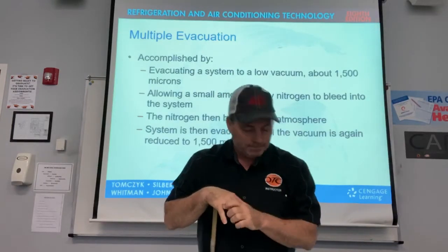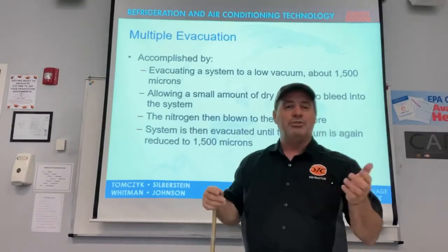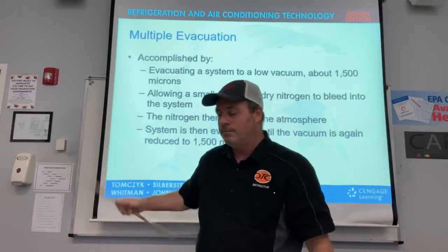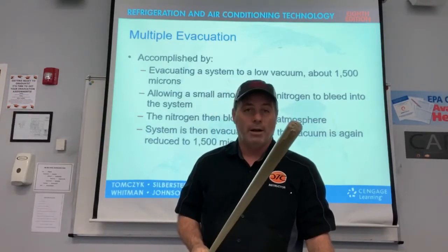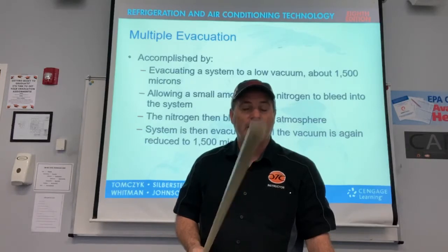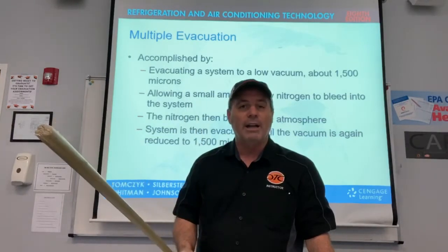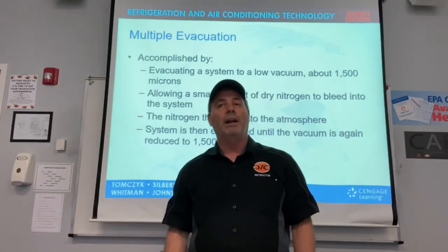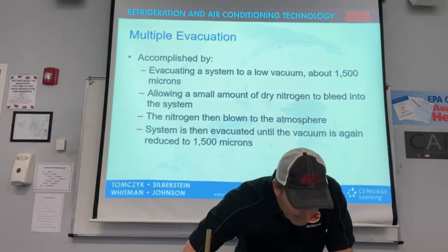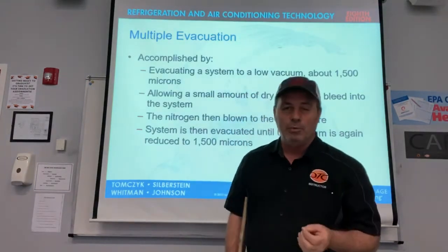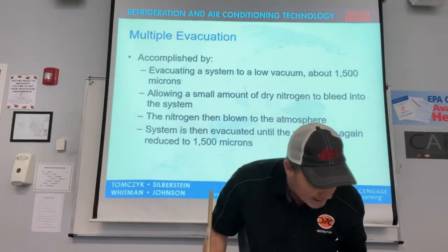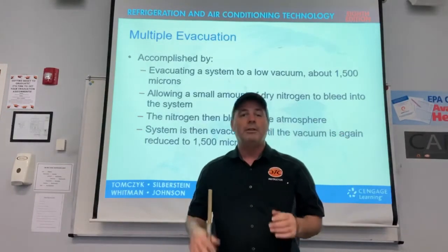You got a leak. Now we'll tell you this, just because you found a leak like that does not mean that's the way you detect leaks. That's a byproduct of running a vacuum and found a leak like that. That's not how you search leaks. You have to fill with dry nitrogen and check all your braze joints and flat joints. That's the proper way. Now, let's say you have moisture in the system and you want to remove it. One way to dehydrate it is to get a good liquid line dryer on there with moisture removal.